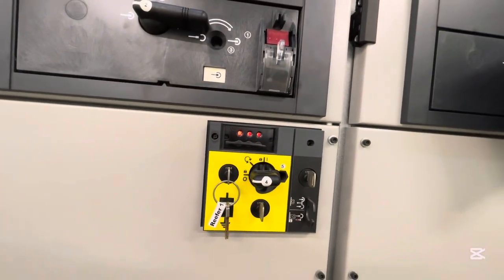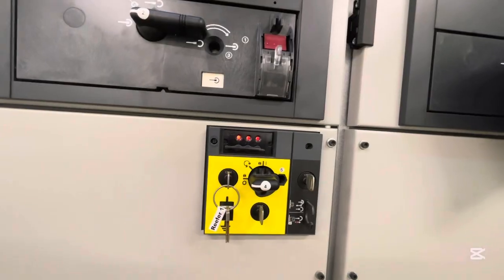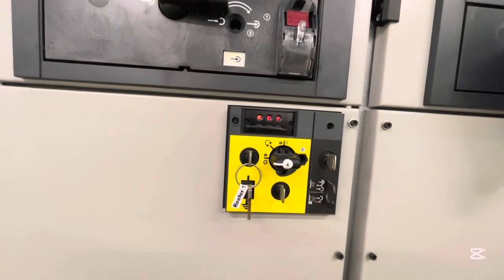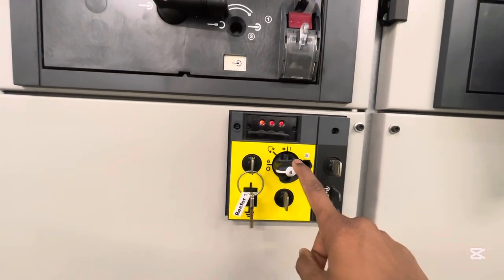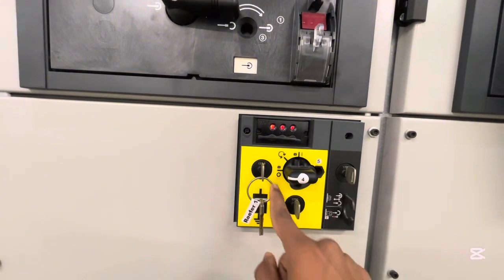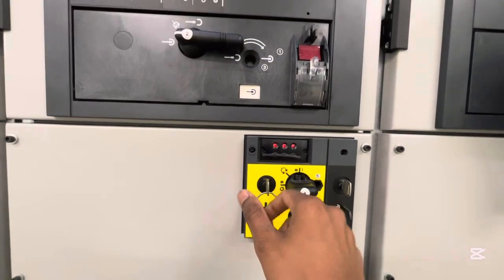Now that you have racked out the circuit breaker, you have to ground it. So in all high voltage ships, for racking out or disconnecting circuit breakers, first you disconnect it, then you earth it. This is the one for earthing.